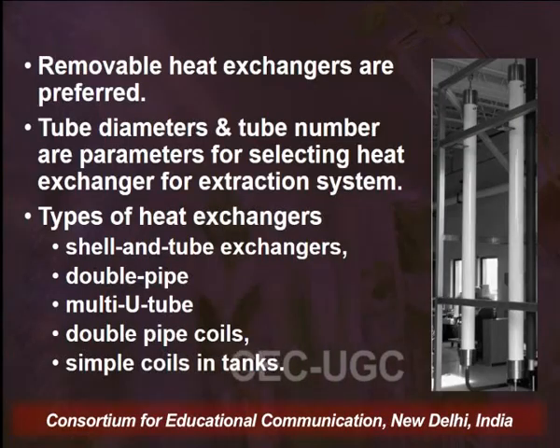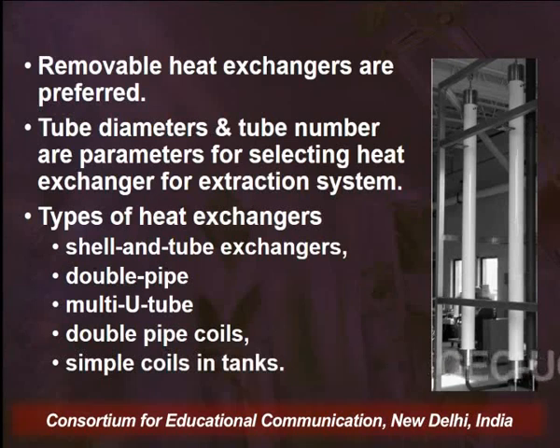There are different types of heat exchangers that are commercially used, and these are shell and tube exchangers, double pipe exchangers, multi-U tube exchangers, double pipe coil exchangers, and the simple coils in tanks exchangers. So every exchanger has its own usage, and they are used for specific purposes. So depending upon the requirement of your process, one can easily select the most suitable type of heat exchanger for their unit. Now we move on to another component, that is piping and the valves.